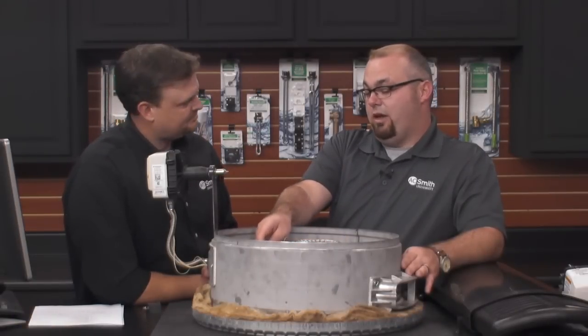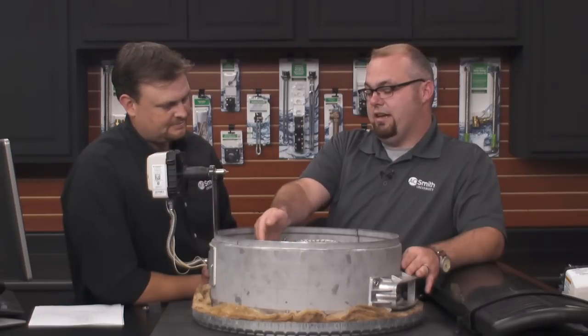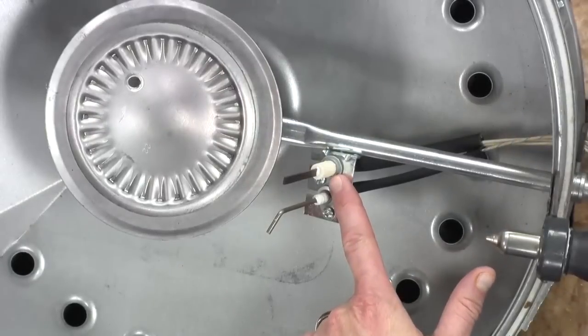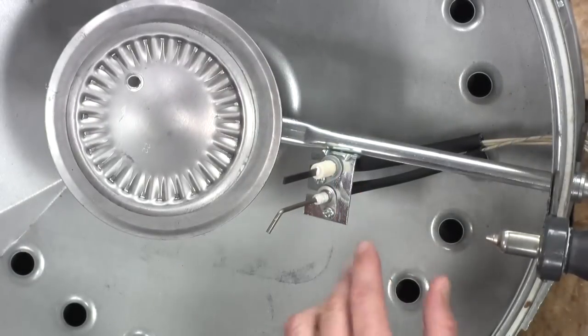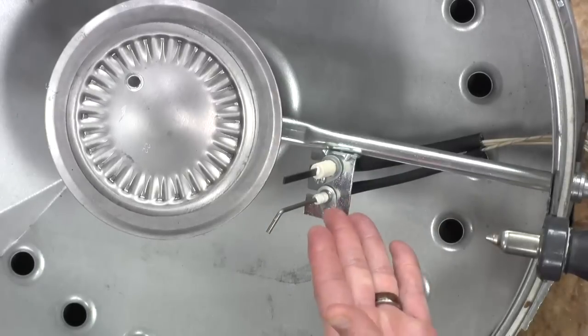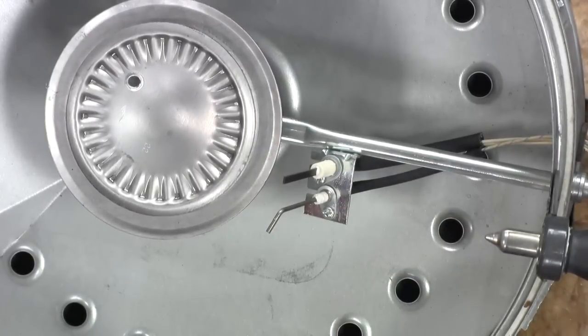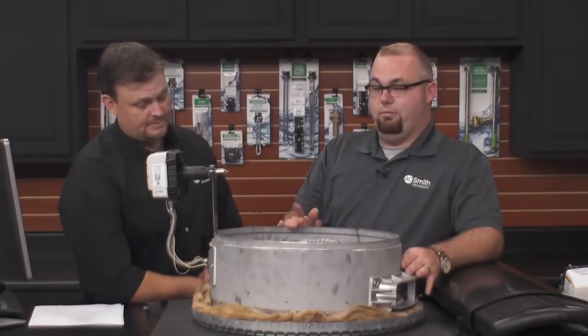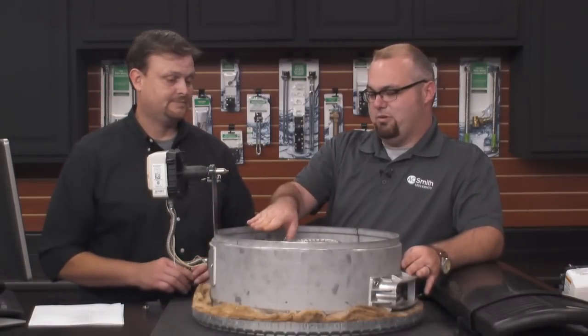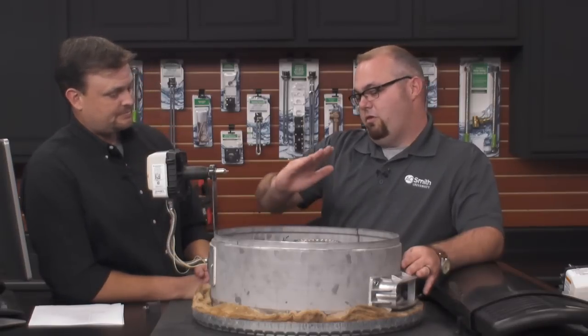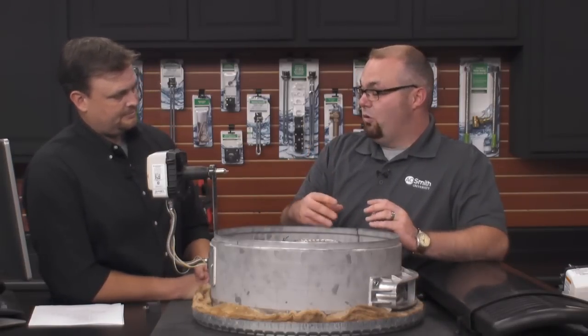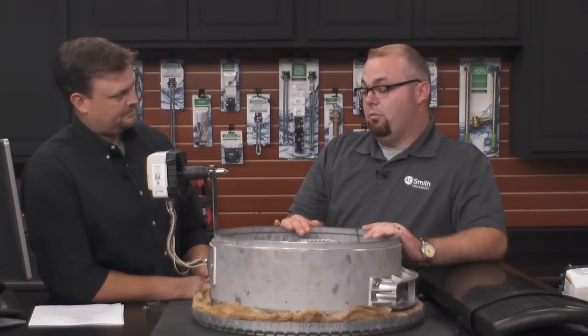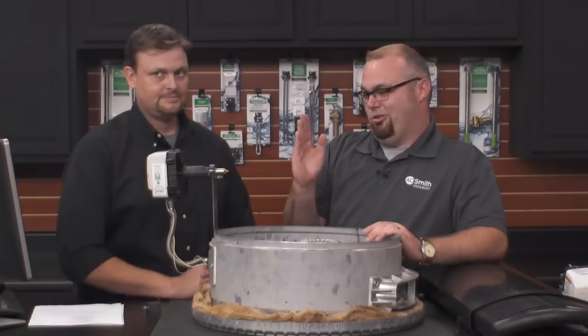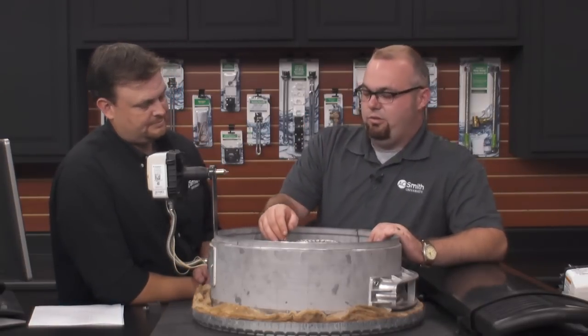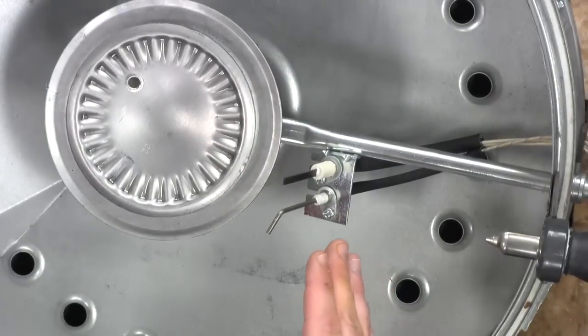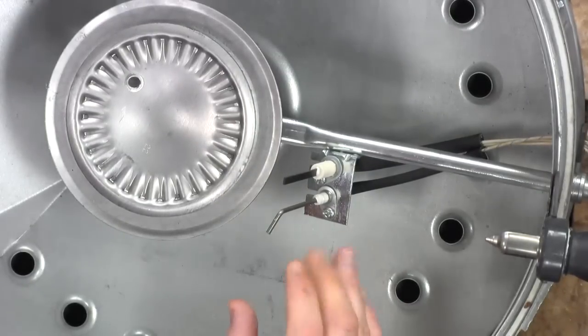Another thing that helps with smooth light off is the orientation of the igniter and the flame rod. We're still using a silicon nitride igniter on this unit. What do you mean, the orientation? We've positioned it differently than we did in the past. Correct. The old school power vent, and you guys servicing this would be very familiar with it, just pretty much points straight out towards the burner. We've moved them like this, which allows a smoother light off. It also helps with condensation falling on it, because it's harder for it to hit if it's pointed up. Overall it helps the way the heater lights off and operates.